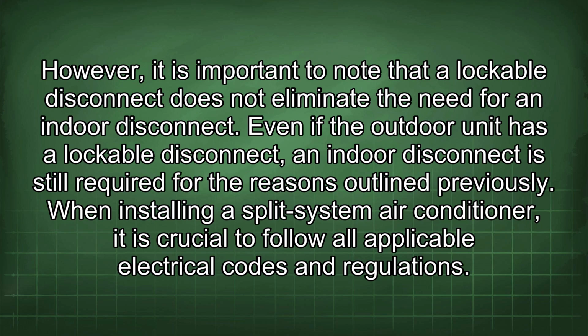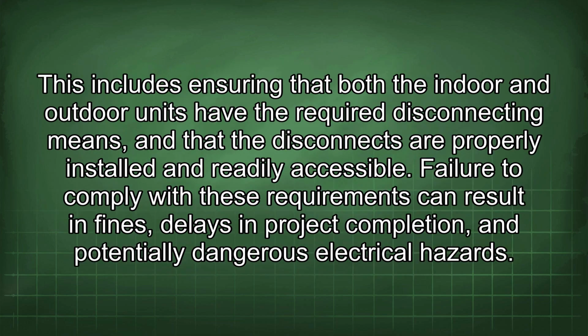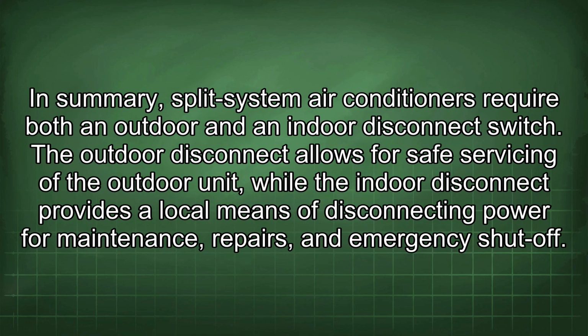Even if the outdoor unit has a lockable disconnect, an indoor disconnect is still required for the reasons outlined previously. When installing a split-system air conditioner, it is crucial to follow all applicable electrical codes and regulations. This includes ensuring that both the indoor and outdoor units have the required disconnecting means, and that the disconnects are properly installed and readily accessible. Failure to comply with these requirements can result in fines, delays in project completion, and potentially dangerous electrical hazards. In summary, split-system air conditioners require both an outdoor and an indoor disconnect switch. The outdoor disconnect allows for safe servicing of the outdoor unit, while the indoor disconnect provides a local means of disconnecting power for maintenance, repairs, and emergency shut-off.